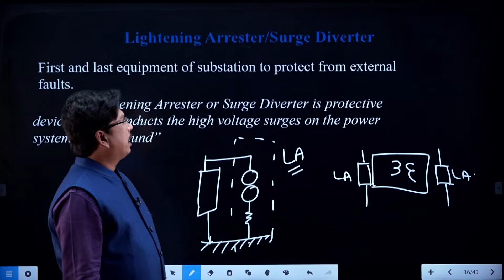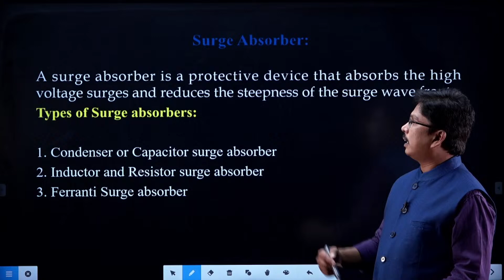And one more element is there, that is the surge absorber. The surge absorber will not conduct high voltage surge to the ground. It will absorb some value of the surge and it will reduce the steepness of the surges. Whenever a surge is grounded through the element, that is called the lightning arrestor. But whenever the surge is not grounded, but still we can reduce the impact of the surge, that is called the surge absorber. There are various types of surge absorbers: capacitor type, inductor and resistor type, and Ferranti surge absorbers. Right, students? That is the next element we can discuss.